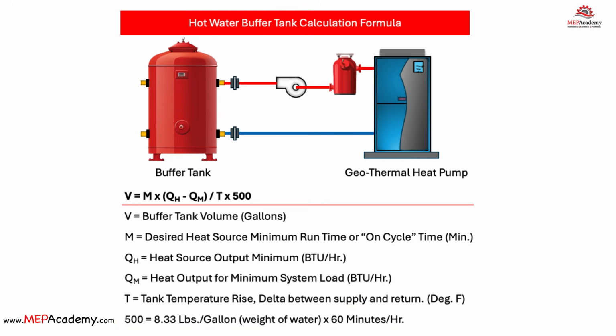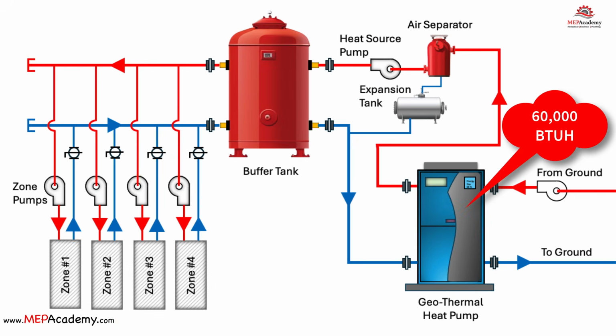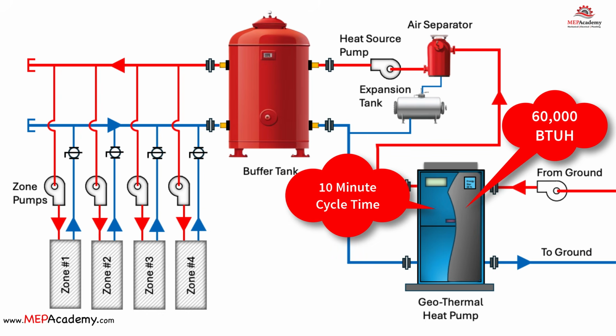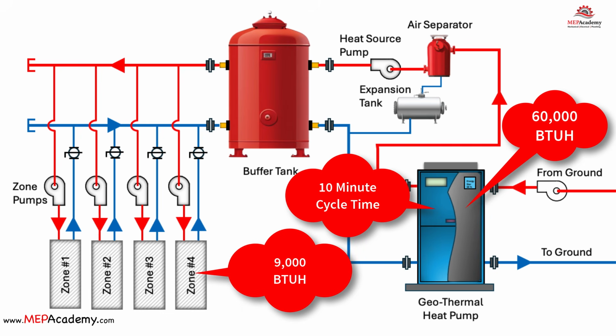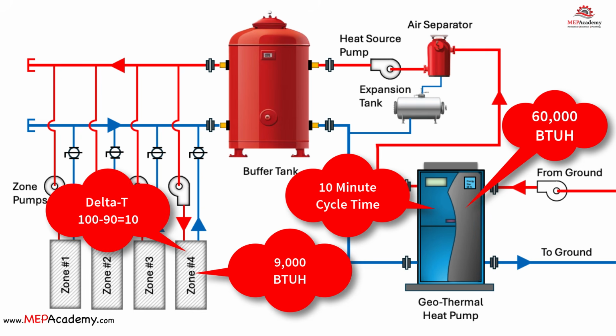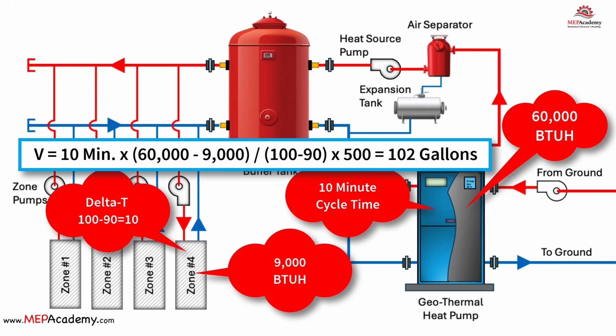For our example, let's assume that we have a heat pump that outputs a minimum of 60,000 BTUs per hour and that the manufacturer recommends a minimum cycle time of 10 minutes and that the smallest zone is 9,000 BTUs per hour and the radiant heating zone's allowable temperature differential is from 90 to 100 degrees Fahrenheit. If zones 1 through 3 were off, and only zone 4 was running at 9,000 BTUs per hour, our calculation would look like this. Buffer tank calculation. V equals 10 minutes times 60,000 minus 9,000 divided by 100 minus 90 times 500 equals 102 gallons.